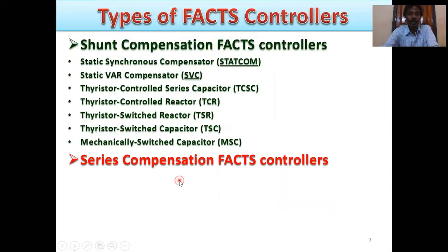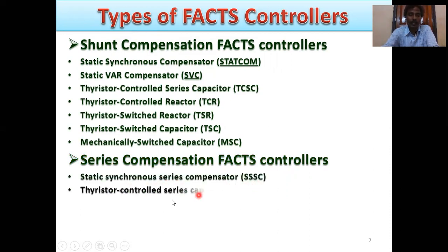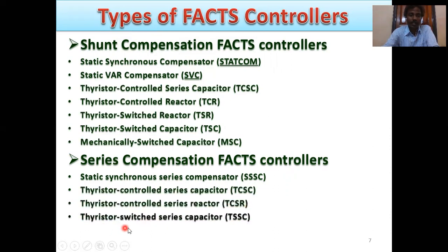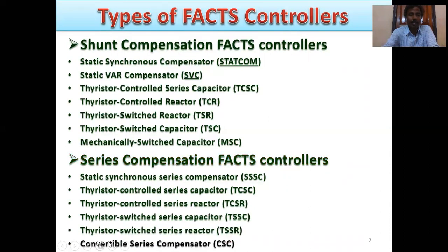controller. Series compensation. The names of the series compensation FACTS controllers are: static synchronous series compensator, SSSC; thyristor controlled series compensator, TCSC; thyristor controlled series reactor, TCSR; thyristor switched series capacitor, TSSC; thyristor switched series reactor, TSSR; and convertible series compensator, CSC.